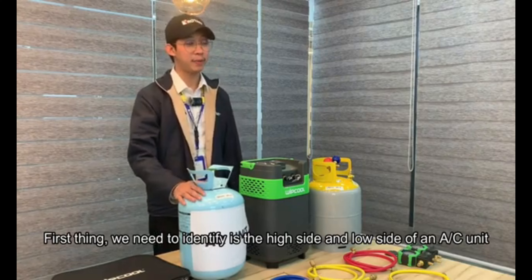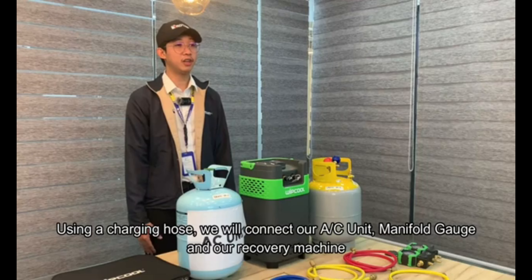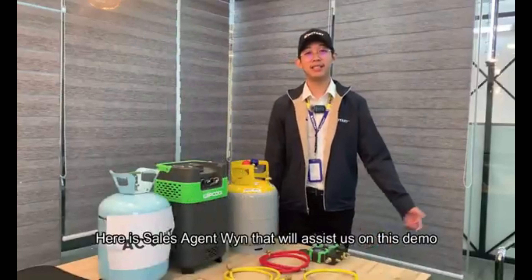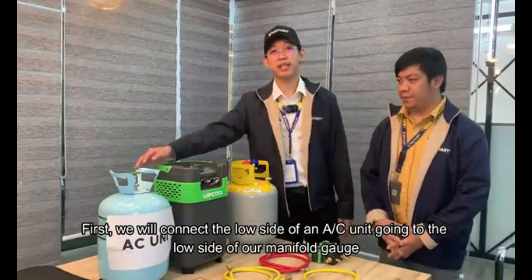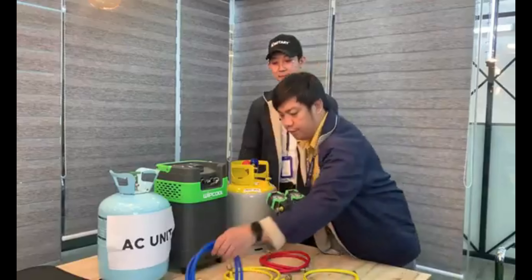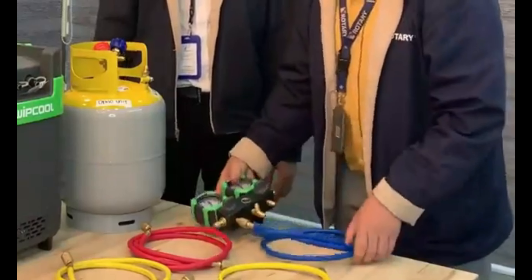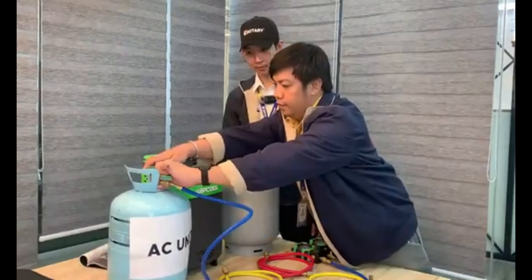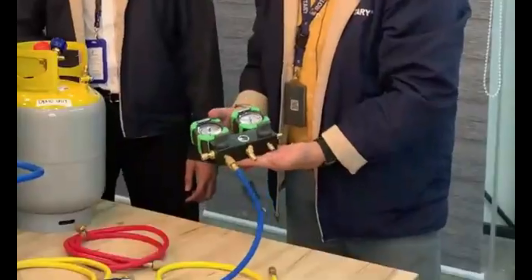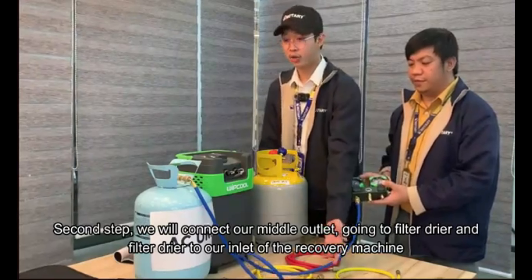The first thing we need to identify is the high side and low side of an AC unit. Here is Sales Agent Wyn, who will assist us on this demo. Using a charging hose, we will connect our AC unit, manifold gauge, and our recovery machine. First, we will connect the low side of an AC unit going to the low side of our manifold gauge. Second step: we will connect our middle outlet going to the filter dryer, and the filter dryer to our inlet on the recovery machine.